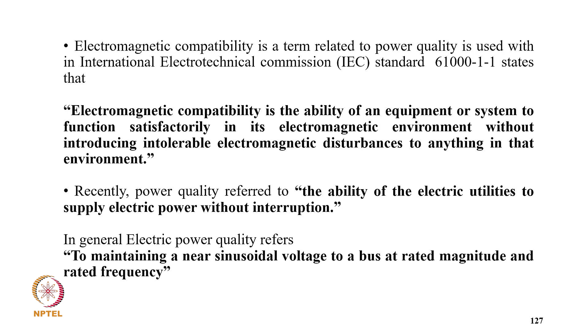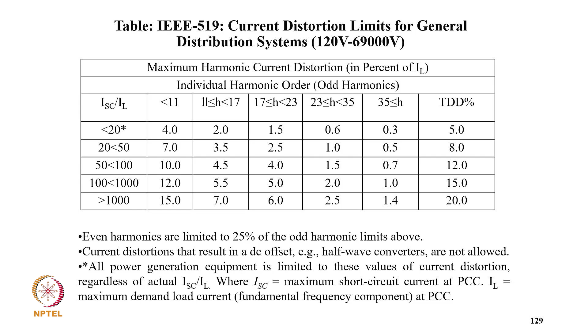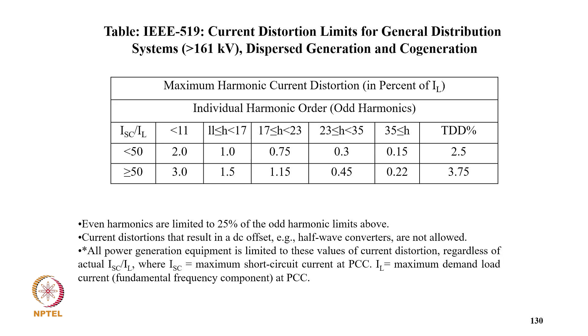Coming to power quality standards, the IEEE 519 has a current distortion limit for general distribution systems from 120 V to 69 kV, where the total demand distortion is 5% if the short circuit impedance is more than 5%. If the short circuit impedance is quite low, less than 0.1%, then it can be tolerated up to 20%, so that the voltage THD does not increase more than 1% at the point of common coupling. This standard also shows the current distortion limit for systems above 161 kV, where it is not allowed to be more than 3.75%, depending upon the source impedance.